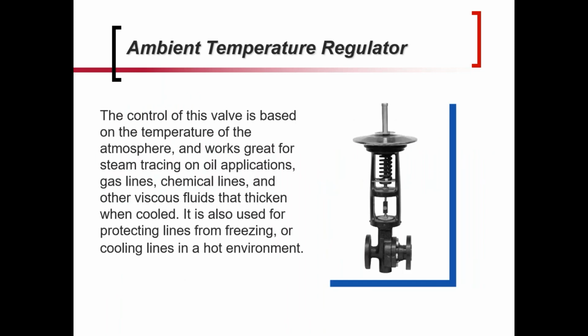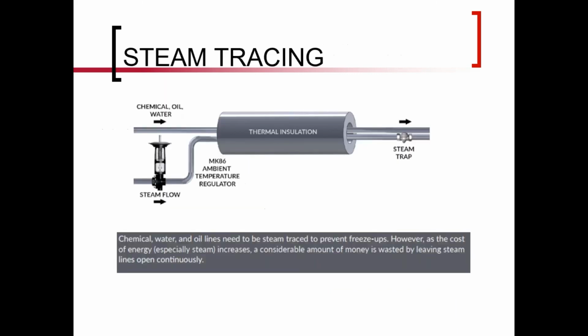That's what it looks like. So this one does not have a capillary. It doesn't have a sensing bulb or anything like that. So just the actuator is what senses the outside temperature and opens or closes the steam tracing line. And something like this will usually easily pay for itself in one winter season. Sometimes even in just the fall if you get some cold snaps in there, because you're not wasting energy at that point.